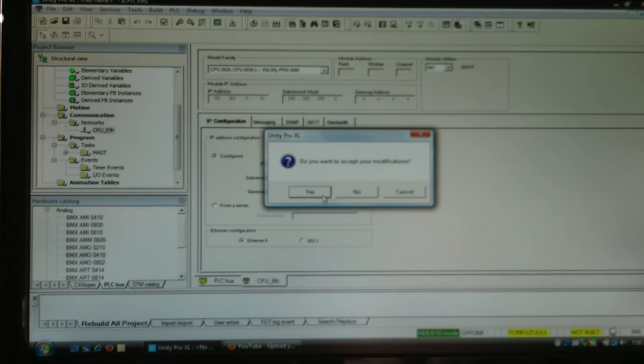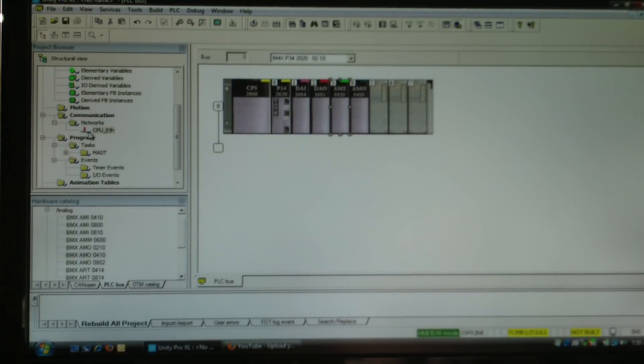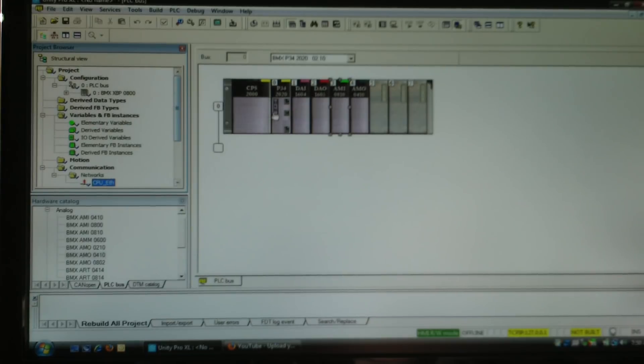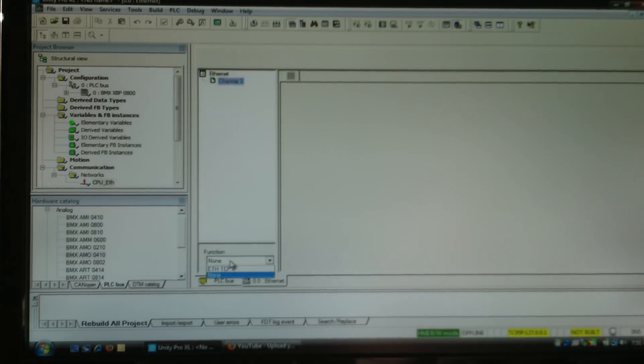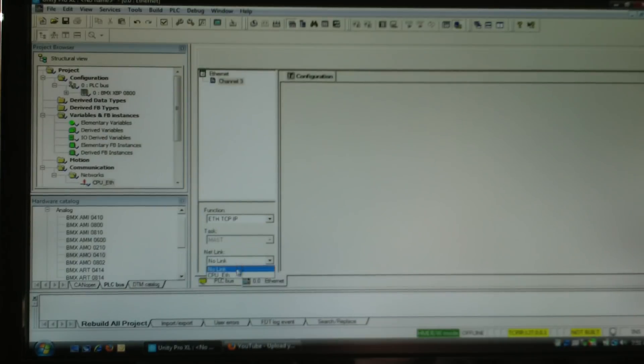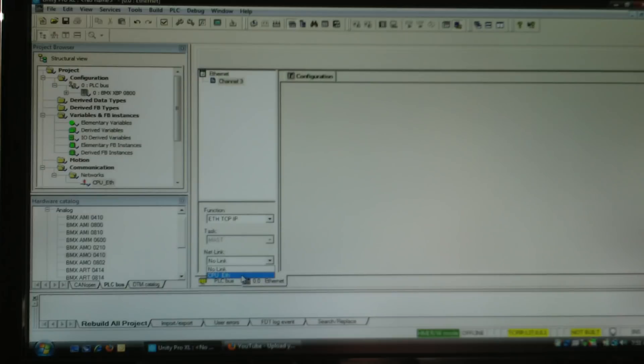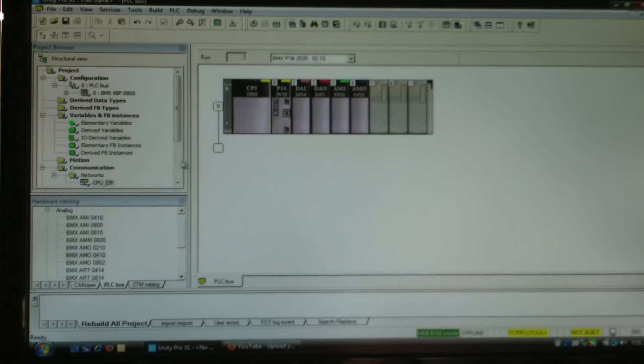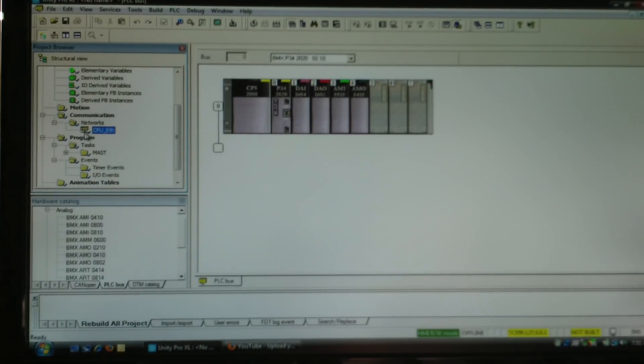I validate and close, and you'll notice a little red squiggly next to my network — that means I have not linked it yet. To link it, go back into the actual physical port of the CPU, click on channel 3, select Ethernet TCP/IP as the function, and link it to 'CPU ethernet'. If you don't have the network you created listed there, it means when you created the network you did not select CPU instead of NOE. Once I select my network and validate, the red squiggly is replaced with a little green check mark.